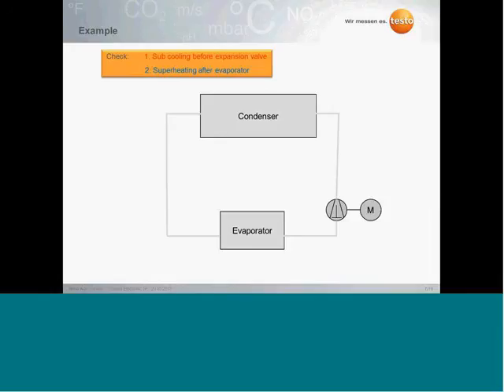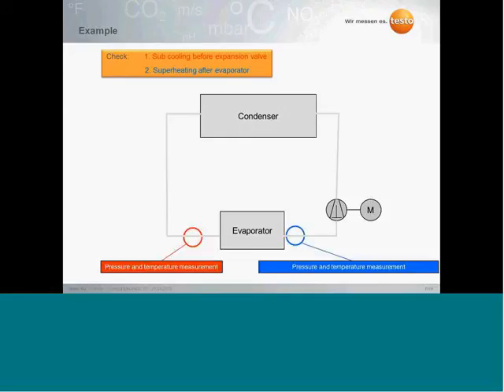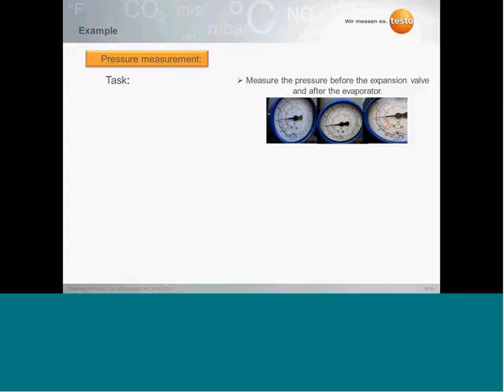As mentioned, I would like to explain the first point, reliable and precise measurement technology, a little bit further. I would like to do this with a very simple example: measuring subcooling and superheating on a refrigeration system, which is of course one of the standard measurements you do when working with a manifold on a refrigeration system. We have to measure the pressure and the temperature for this, and I would like to go with you step by step through the measurement to check what possible failures can occur when using the wrong equipment, bad equipment, or the equipment normally.